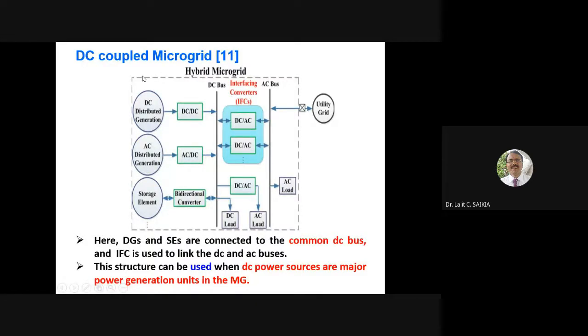But this microgrid sometimes needs to be connected with the utility grid, so we have to connect AC - there must be one AC bus here. This AC bus gets power from the sources - DC DG, AC DG, storage element - via the DC bus. To supply power to the AC bus, it is converted again, DC to AC, and connected to the AC bus. Now this AC bus is connected to the utility grid.